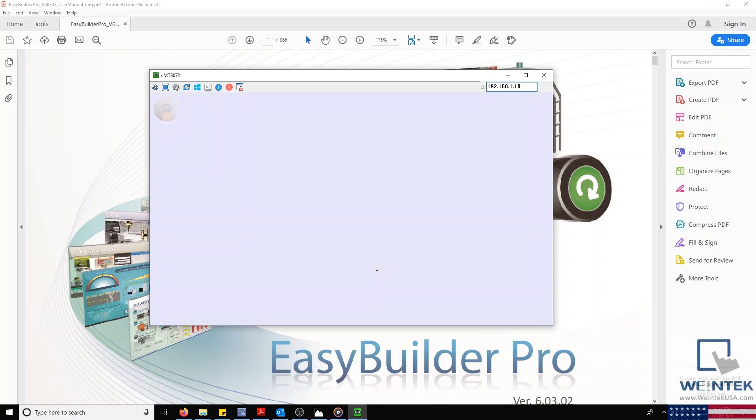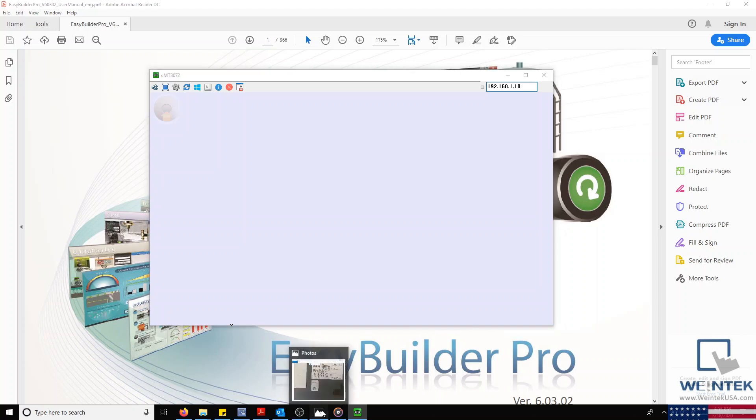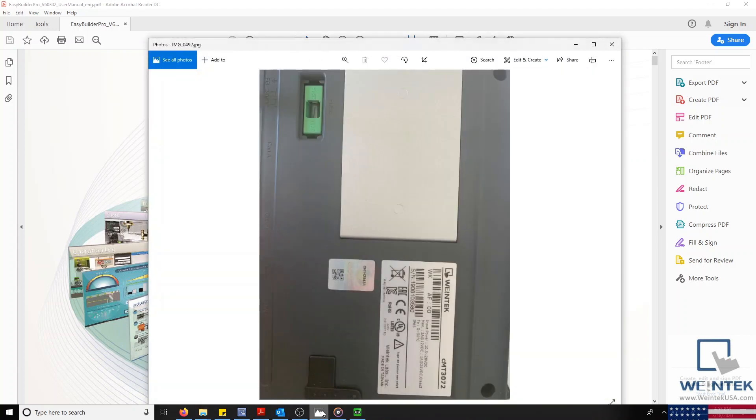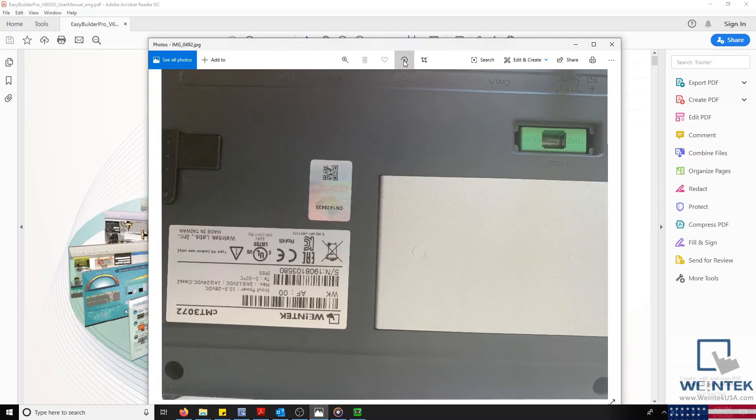Before establishing an Ethernet connection between your HMI and computer, it's important to know if your HMI is CODESYS activated. If your CMT is CODESYS activated, then LAN port 1 on the HMI will belong to the CODESYS application and cannot be used to download an HMI project.